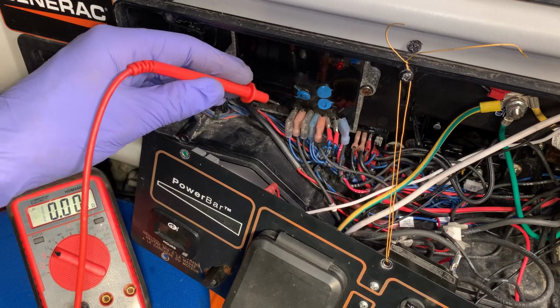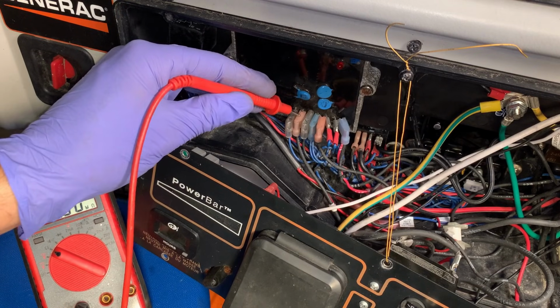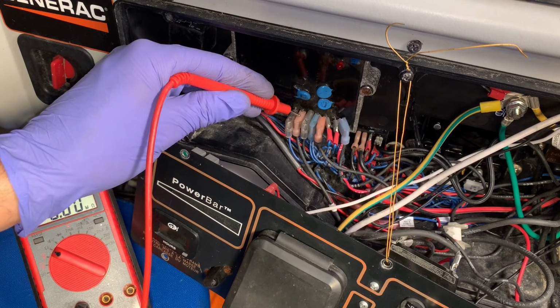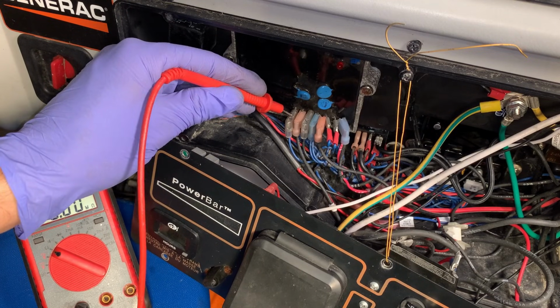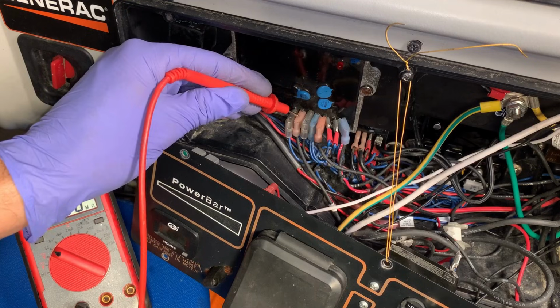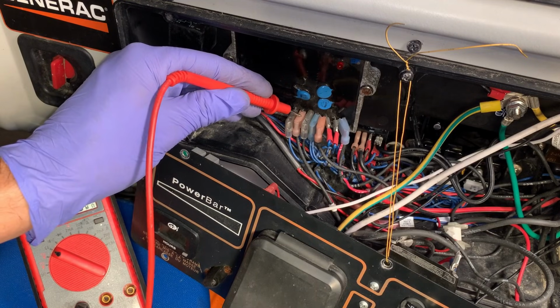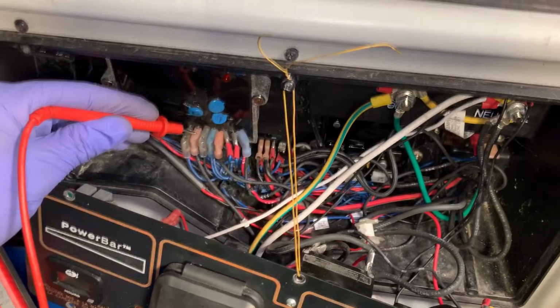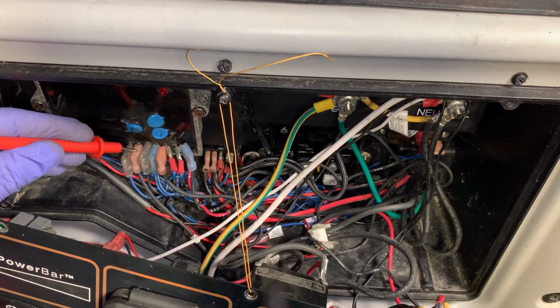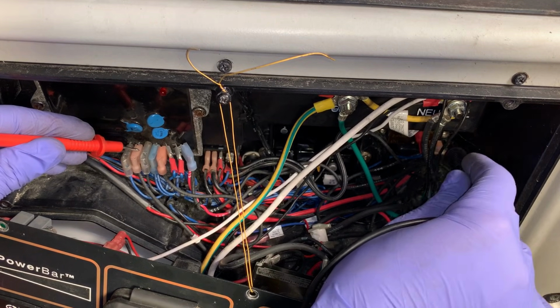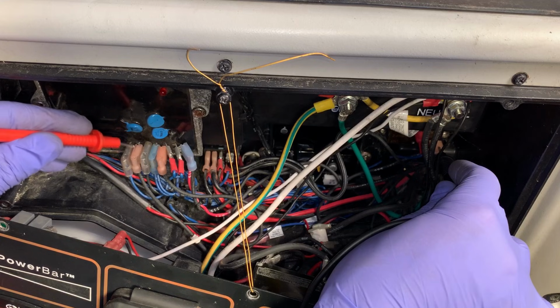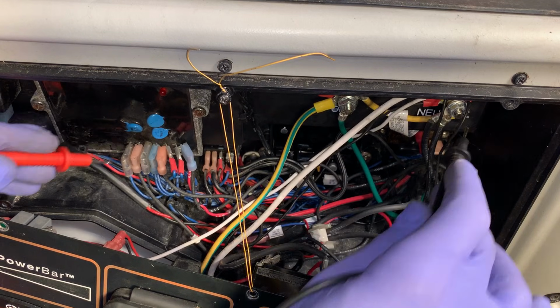I'm going to do one more check here. This wire goes directly to the winding in the stator, and this one's fused. I'm going to pull this terminal off, test directly here, then the other end is on the fuse, which you probably can't see right here. I'll pull that off, pull this off, and we'll check it again.